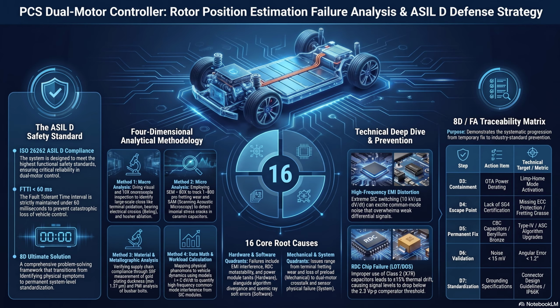Right. Precisely. That oxygen spike basically confirms that the protective noble metal plating has been physically sheared off by microscopic vibration. Just rubbed right off. Yeah, and that exposes the base copper alloy to whatever trace atmospheric oxygen is trapped inside the housing. And then it rusts, basically. Well, the resulting oxidation forms an insulating layer, which fundamentally alters the contact resistance. We will get into the catastrophic chain reaction that causes shortly, but the microanalysis goes even deeper than surface chemistry.